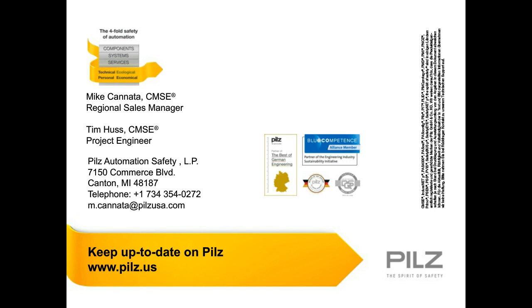I may have missed this, but can a door interlock be used instead of a lockout switch with the system for routine maintenance? If so, what are the advantages? Typically they're used in conjunction with the door lock, but that's not part of the isolation system. So the isolation system is designed to be a disconnect replacer. Of course, your disconnect has nothing to do with a guard door switch. The standard allows our system to be integrated with the standard safety controls on a machine separately. So there is a separate connector on the panels to interface to your safety control system. Could be anybody's safety PLC or relay-based system.